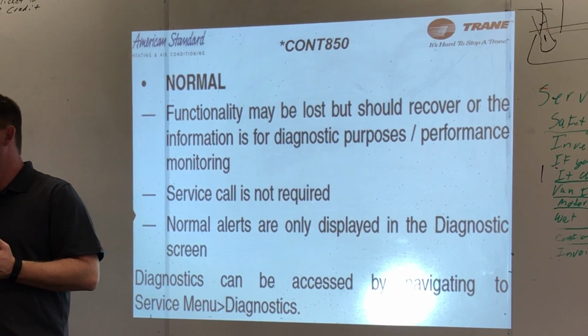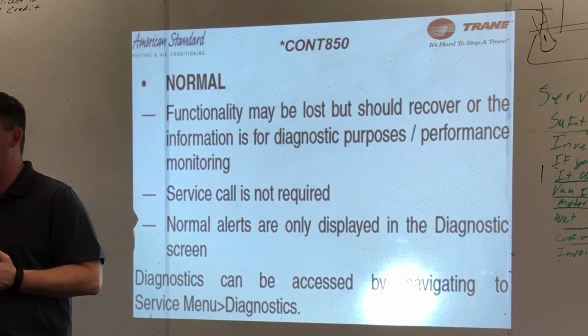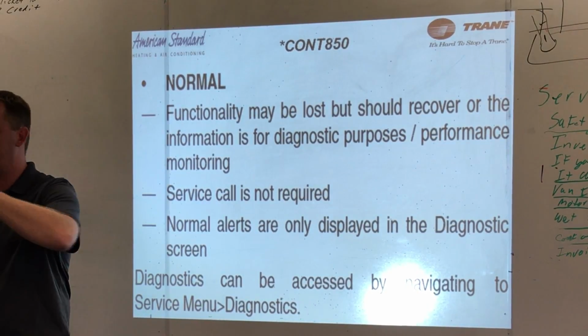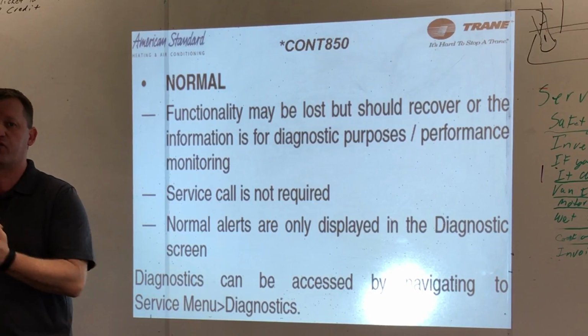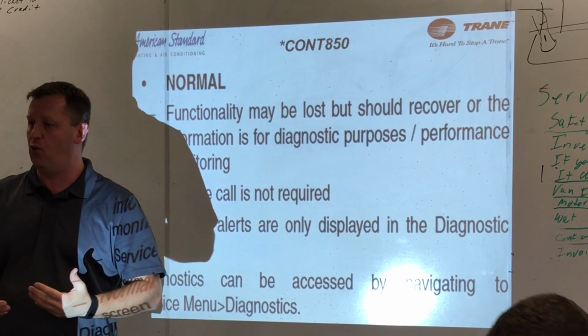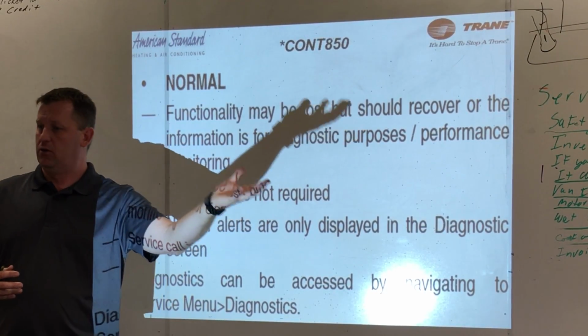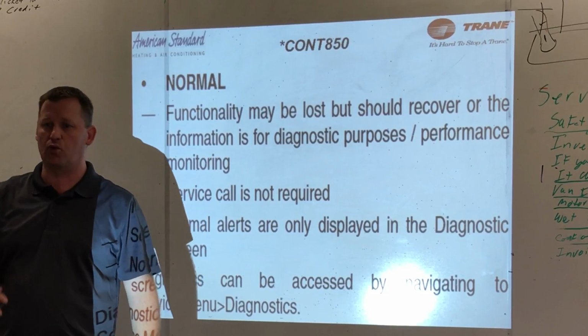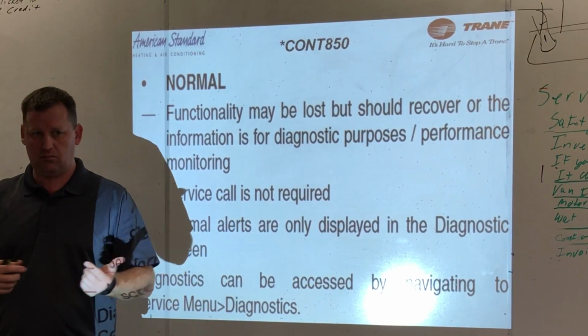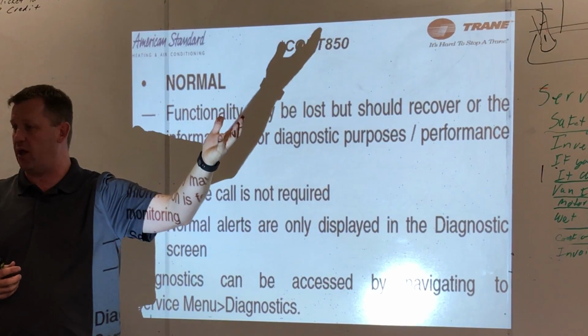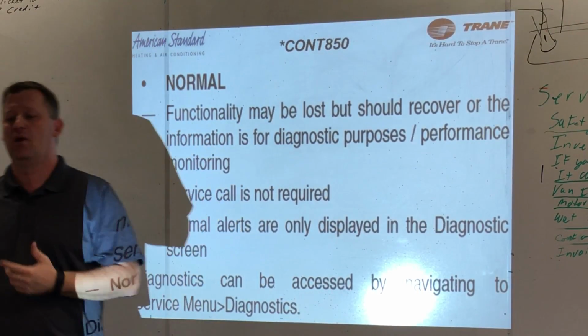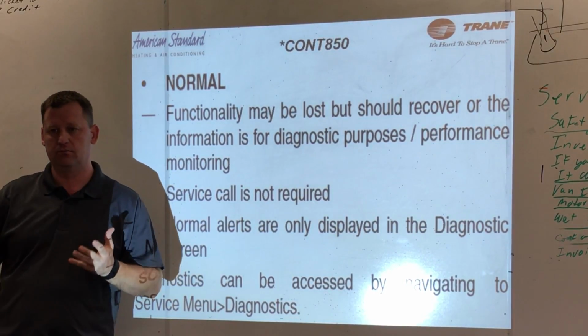Below that 78 PSIG for 10 minutes creates the indoor coil frost protection, because 78 psi is 28 degrees. Once we've hit 28 degrees for 10 minutes, it says, okay, we're freezing up our coil. It sends an alert to the stat, saying we're shutting down for coil frost protection, and it's purely low ambient. This is normal when we're below 65 degree ambient temperature and we're cooling, especially if we're trying to run a room temp of 65 degrees. Our residential air conditioners are not made to hang meat in a house, right? Okay, so we have those homeowners that are peculiar.